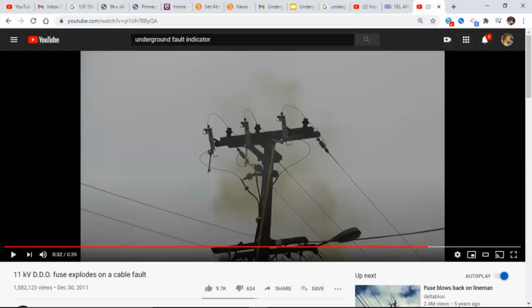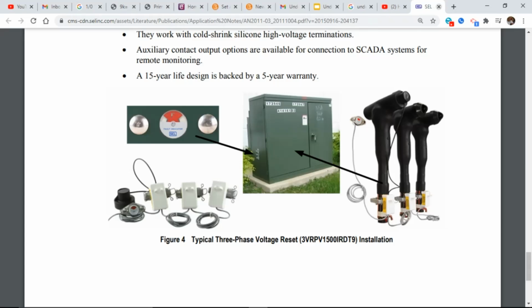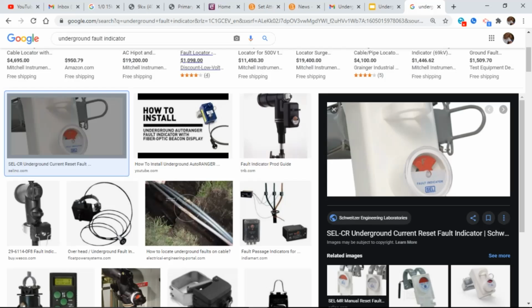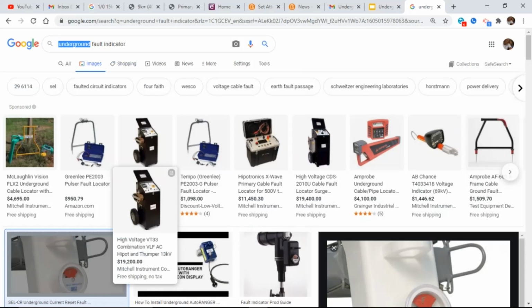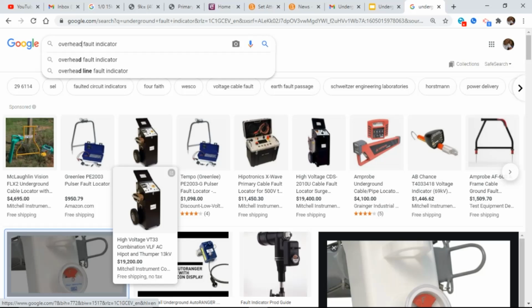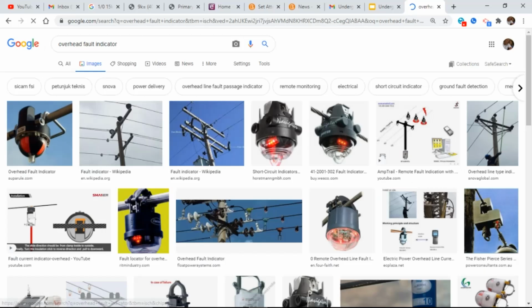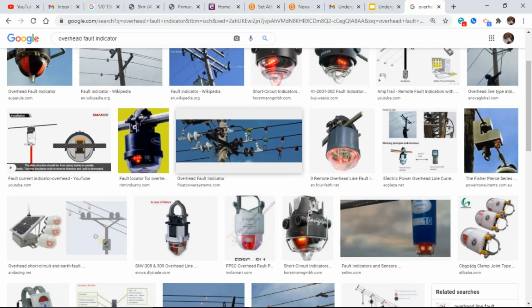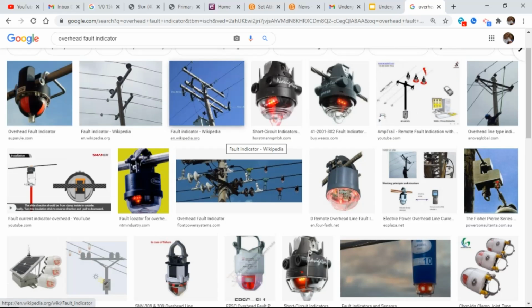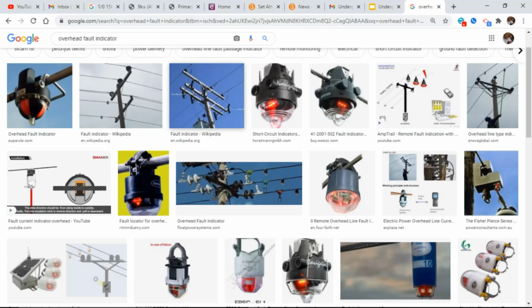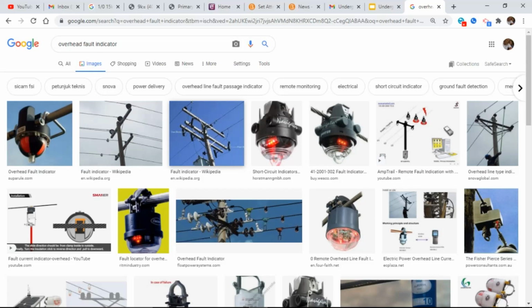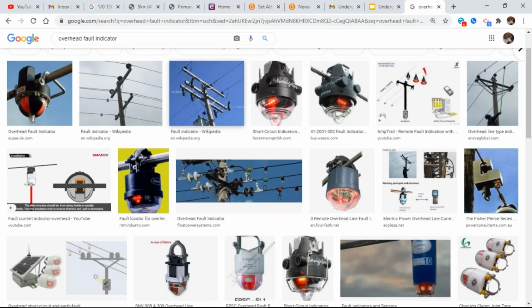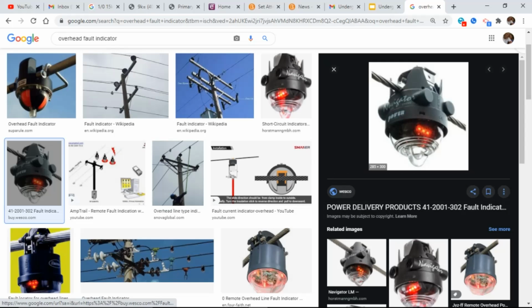Yeah. All right. Just as a heads up to let you know out there, we started using them pretty regularly. And in case you see them in the field, even if you see one now, they got smart and they did overhead fault indicators also. So you can actually go out on line sections that are extraordinarily long, or you've got a line section that goes deep into the woods off a main feeder line, you can install fault indicators on overhead conductor also. And obviously anything beyond the point of the fault indicator, you're going to get a red flashing light.